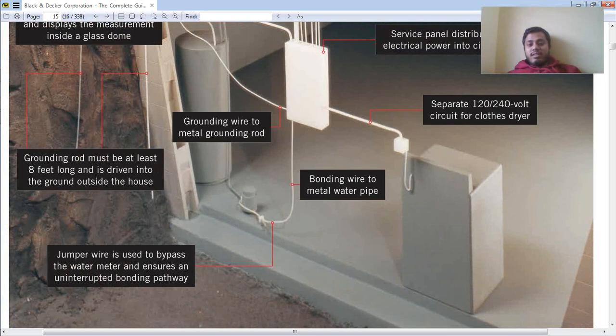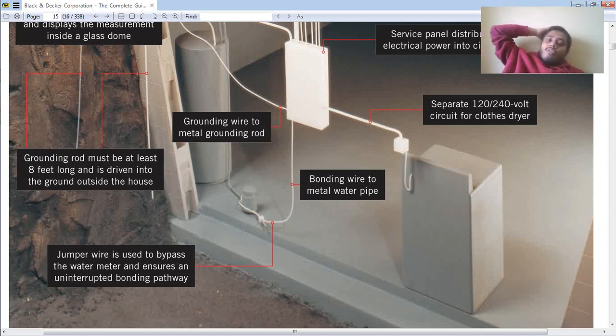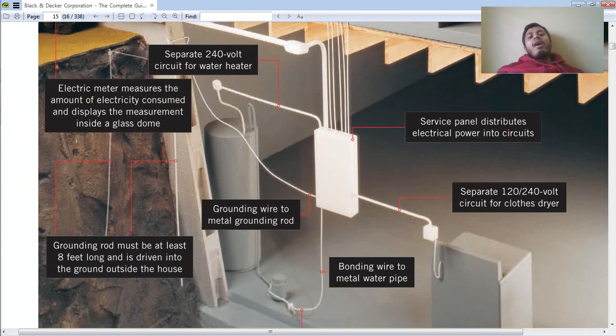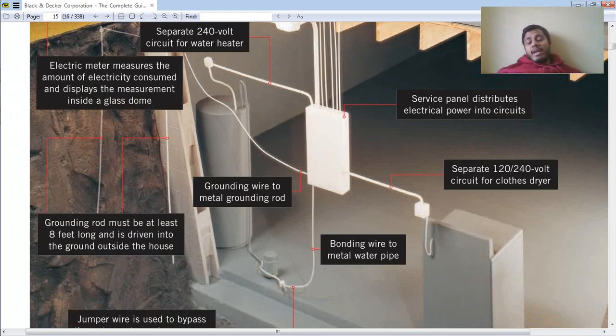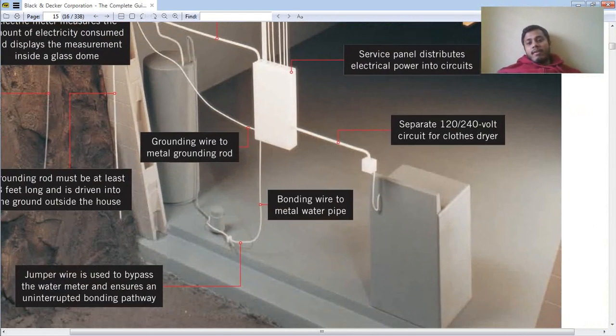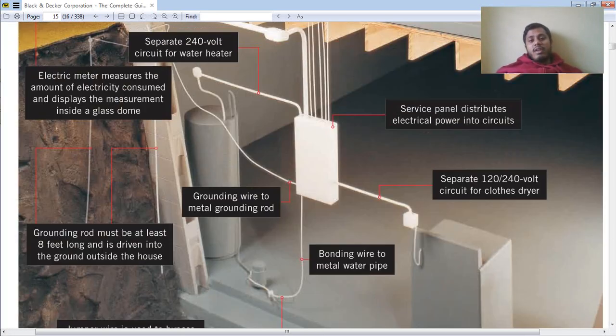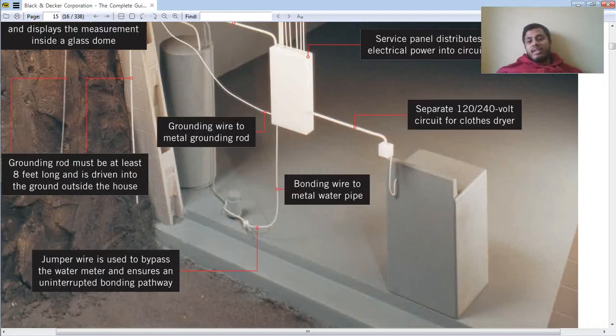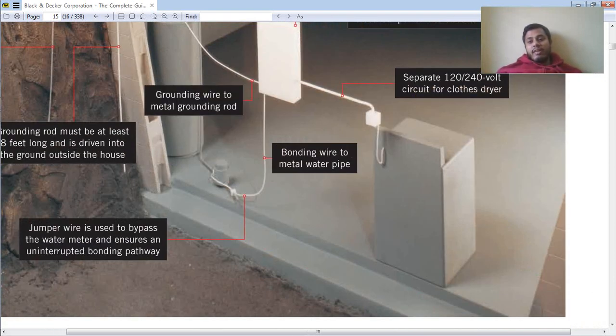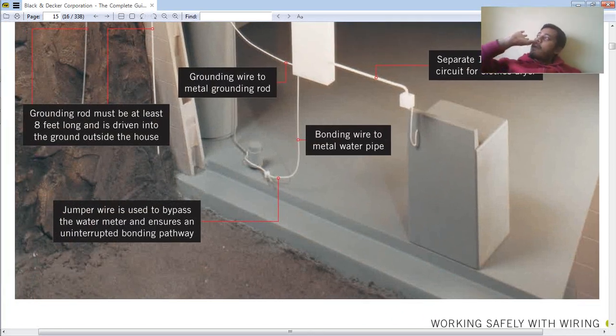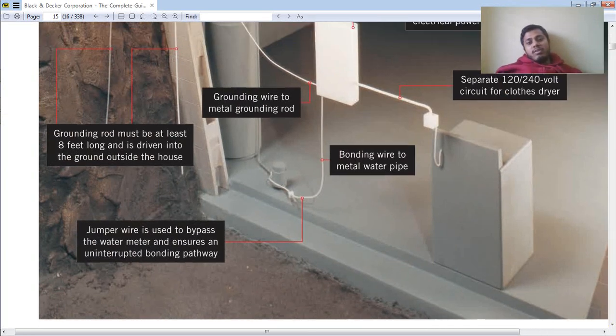Here is another separate device. We separate them because we use dedicated MCBs for security purposes, and the cable type will also be different. We'll learn soon what is inside and how we design for this. So here is the separation: 240 volt circuits for the water heater, and 120/240 volt circuits for the clothes dryer, because heavy loads like AC, geyser, lift and motor all need a separate connection. So this is what separation means.